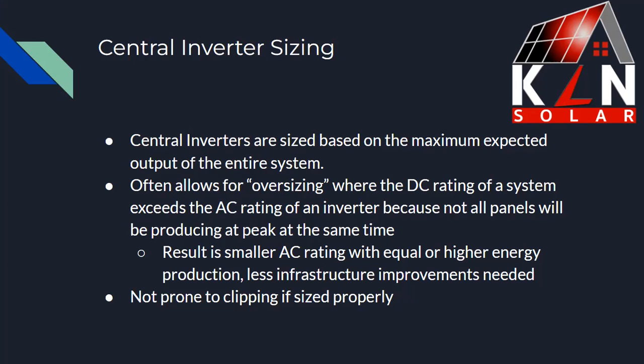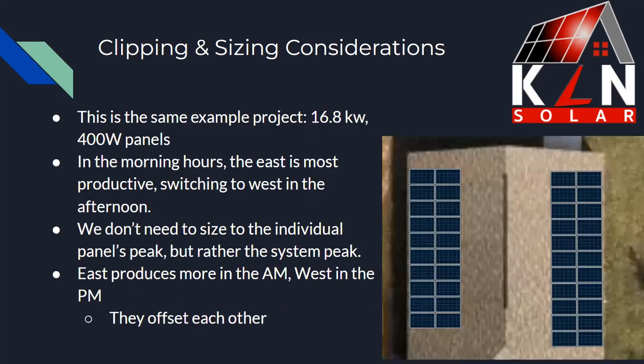How do you size a central inverter? Here you're looking at the maximum expected output of the whole system. This allows for oversizing, where the DC rating of the system is larger than the AC rating of the inverter, because not all panels are going to be producing at peak at the same time. Because of this, you get smaller AC ratings with equal or higher energy production, meaning less infrastructure improvements and the ability to sometimes avoid main panel upgrades. If sized properly, these inverters are also not prone to clipping. Going back to our 16.8 kilowatt case study — in the morning the east produces, in the afternoon the west, but they offset each other.